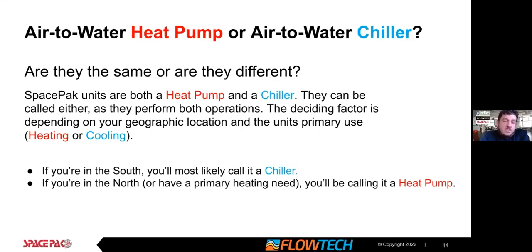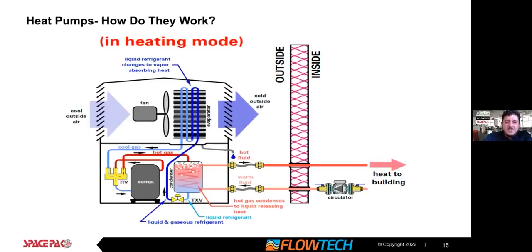They provide heating and cooling depending on their mode of operation. And so it's kind of a funny thing to engage with a little bit too with people when they're talking. Here's an exploded diagram of the equipment, the SpacePak units here, and air-to-water heat pumps in general. And a heat pump doesn't create heat. It uses electricity to gather heated energy or cooling energy. In our case of the monoblocks, it's injecting it into the water stream and pumping into the house.